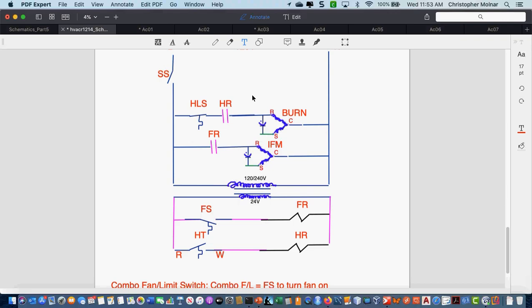Relay? Yeah. What happens if my system is not calling for heat and for some reason, I'm going to do this in red, what happens if that relay fails in the closed position? Stays on. Okay, I'd be very concerned if I had a burner motor that was continuing to run. There's just too much that can go wrong. That's why I usually try to put my limit switch on the high voltage side in the path of the burner motor.